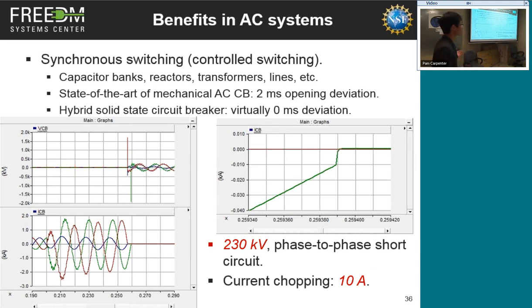A typical value would be about 10 amps. So as the current is oscillating and comes close to zero, but not exactly zero, at the 10 amp level it interrupts the circuit. That's not a good thing, because at that moment the system still has a lot of energy.